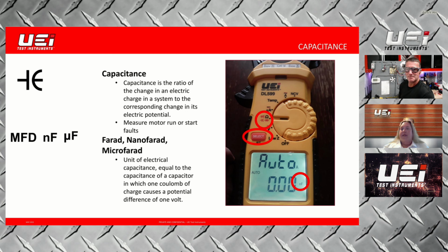Capacitance is read in farads. When we look at an actual capacitor, it'll tell you its value in microfarads, and it'll have its plus or minus markings on there. It's one of the simplest things we can test to make sure things are running properly. We're going to grab a capacitor test beforehand—most importantly, make sure our voltage is off. One of the neat things about the DL500 series we're highlighting here is that we actually sped up the amount of time it takes to read capacitance.